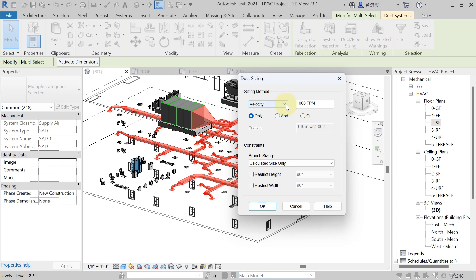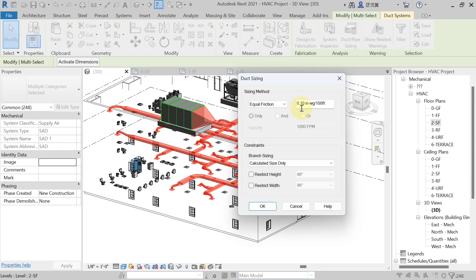Choose your sizing method. Different methods are available: Equal Friction, Static Regain, and Velocity. Here I am using the Equal Friction method — at every 100 feet of duct length, 0.1 inch of water gauge friction loss. Remember, friction loss values vary by project type: for residential, up to 0.08 inch WG; for commercial, 0.08 to 0.1 inch WG; for industrial, 0.1 to 0.15 inch WG per 100 feet. This is a commercial project, so I am taking 0.1 inch of water gauge.